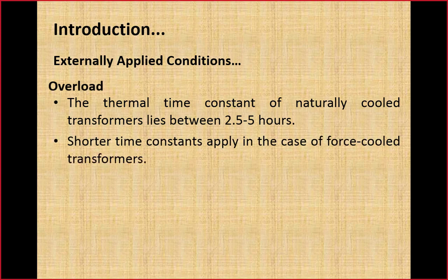Remember, short time constants apply in case of a forced cooled transformer. Large power transformers, although we are using forced oil and air circulation cooling mechanism, cannot be overloaded for such a long duration as a naturally cooled transformer. The reason is that those power transformers produce too much heat losses in volume. So if the heat is not properly conducted into the environment, then the temperature of those transformers will rise to a dangerous value.